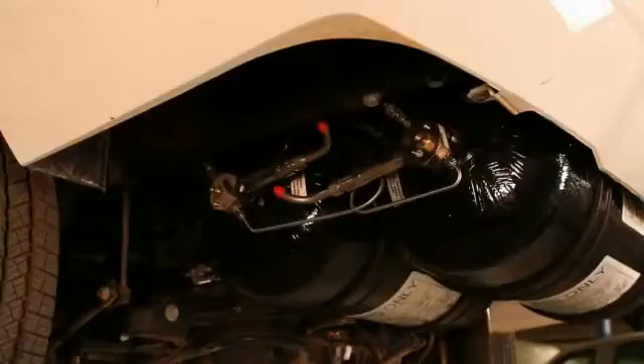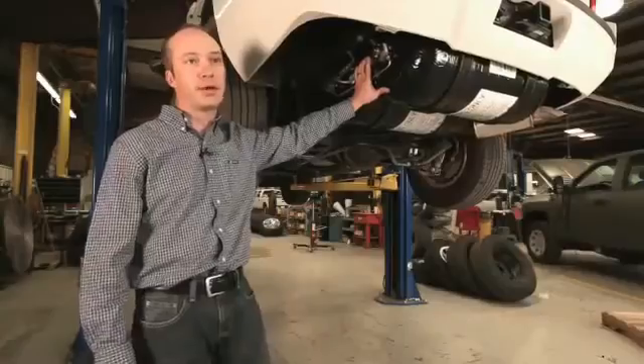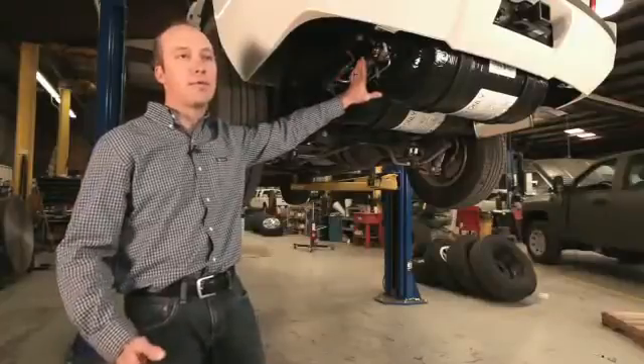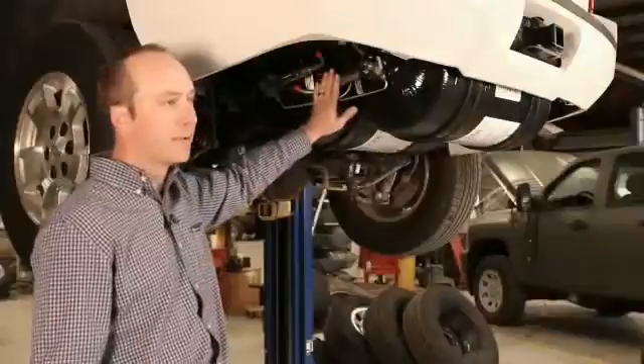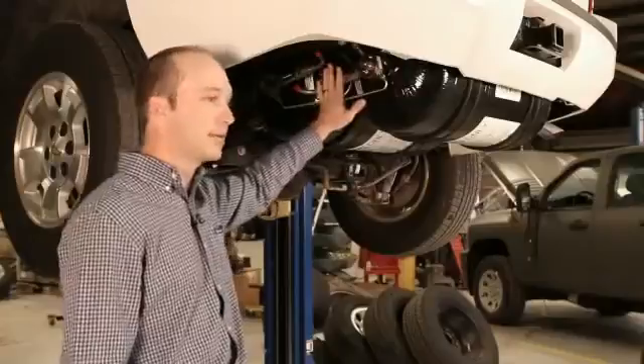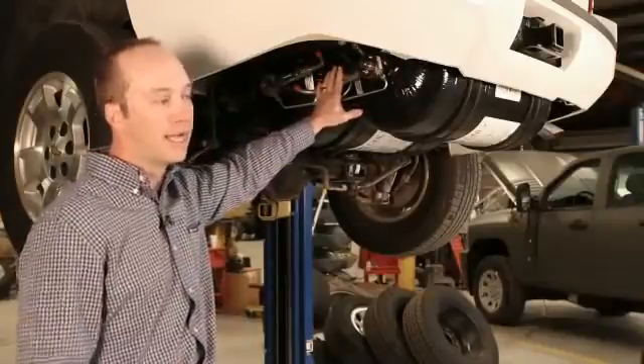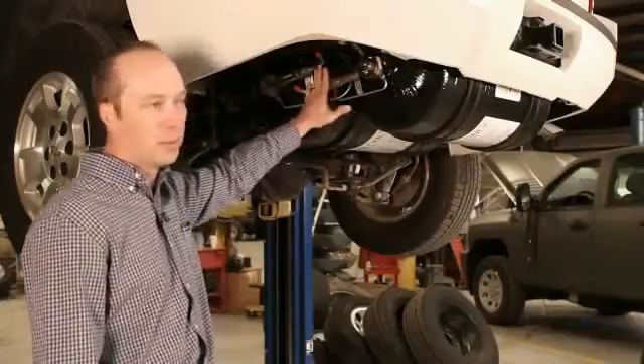In the event of overpressuring the tank, whether from filling or heat, it will release through the PRD. The operating pressure of these tanks is 3,600 PSI. If the device sees pressure exceed 4,500 PSI, it will release and vent to the atmosphere. Additionally, inside the pressure release device there is a heat disc that will burst if temperature exceeds 255 degrees Fahrenheit — so in the case of an engine fire or any extreme heat, it will also release.